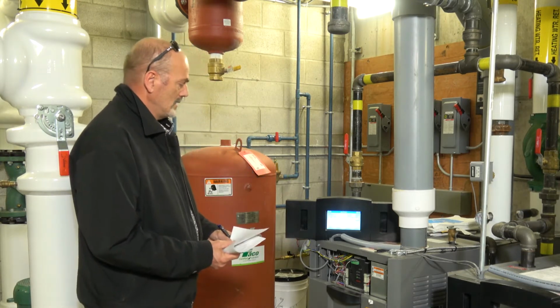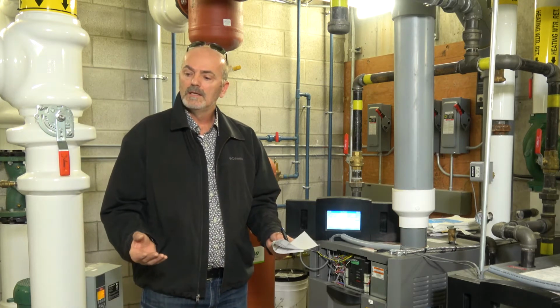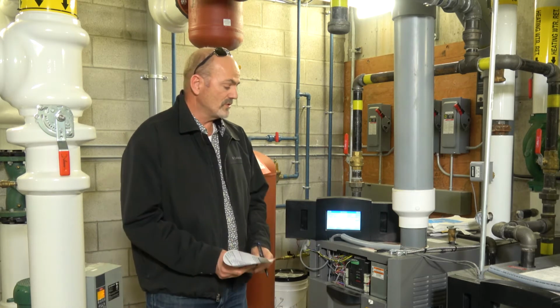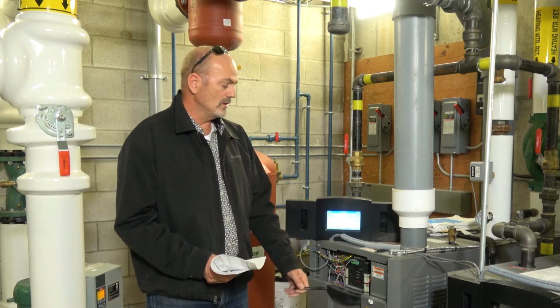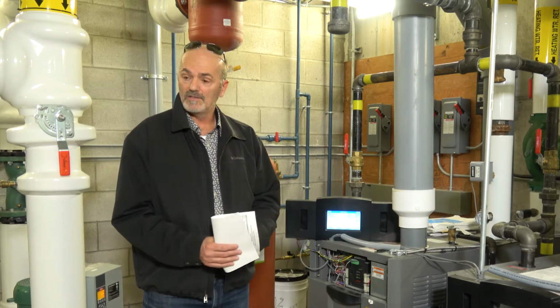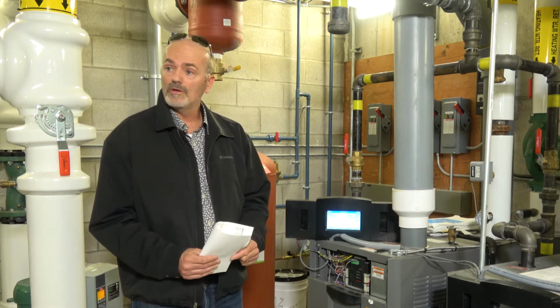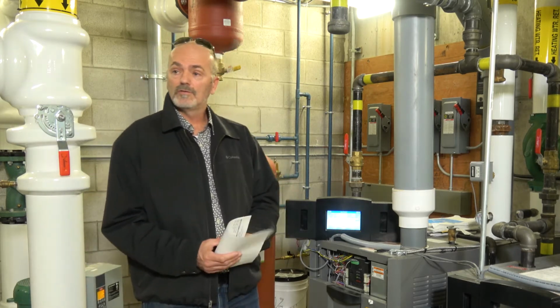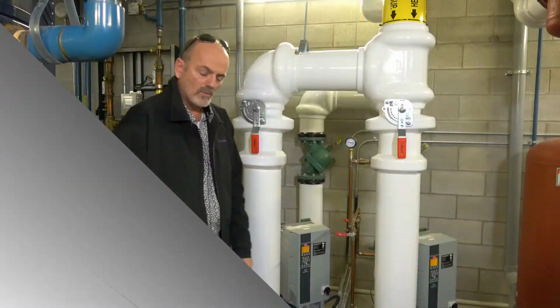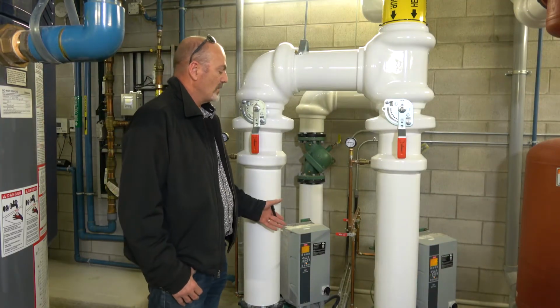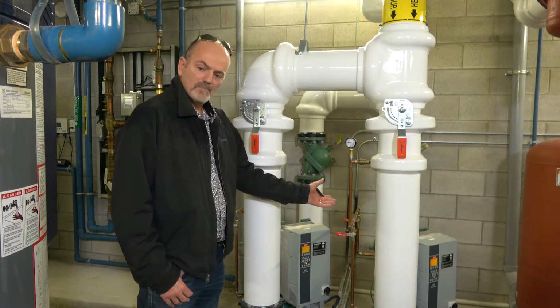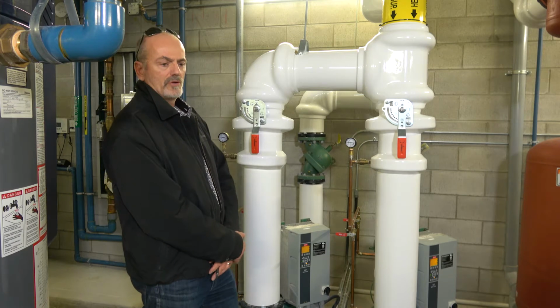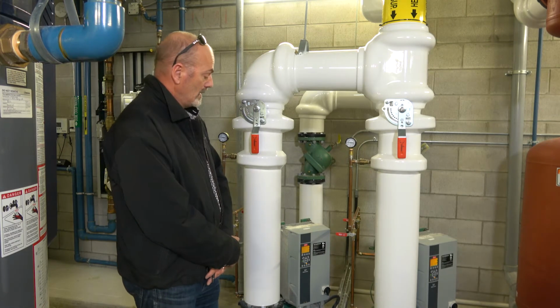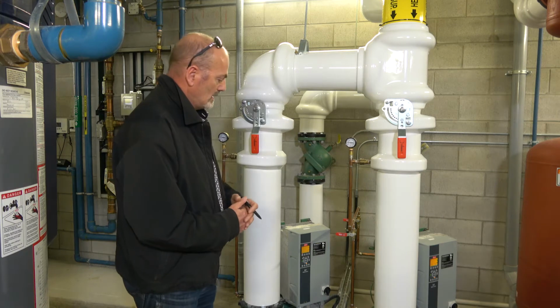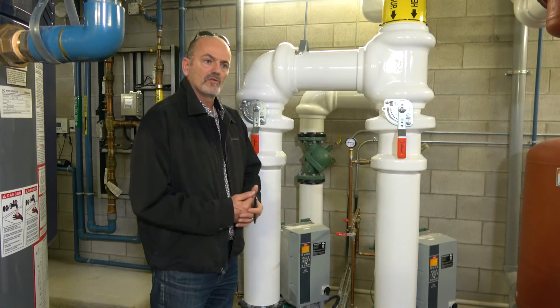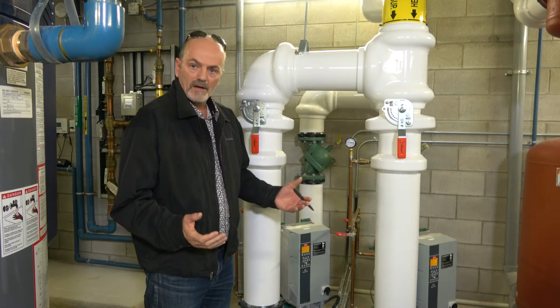Okay. Other than that, if there's faults that you can't address by strictly resetting on the face of the control or resetting the power to the device or to the boiler, then that's when you call in your outside maintenance contractor, a service contractor with all the requirements. What we have here is the primary and backup main heating circulation pumps for the building. These pumps work together to provide the hot water distribution throughout the building to heat all the fan coils.